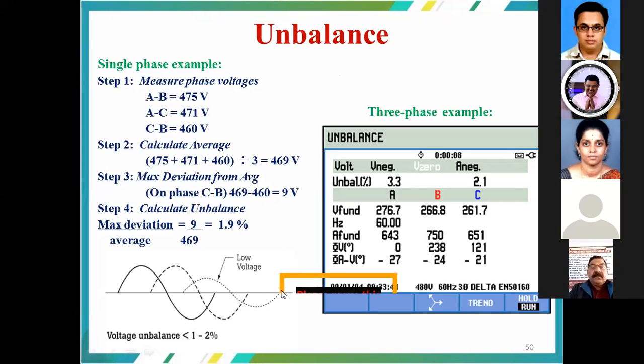So again, this will affect the system performance when we are going for the three-phase system. In the pictorial representation, the A phase and B phase are going to have the waveform like this, whereas the C phase is going to have the waveform of reduced magnitude. Therefore, the unbalance is going to be there. And as far as the standards for the unbalance prescribed by IEC as well as the IEEE, it is 1 to 2 percent, and again it depends on the geographical location.